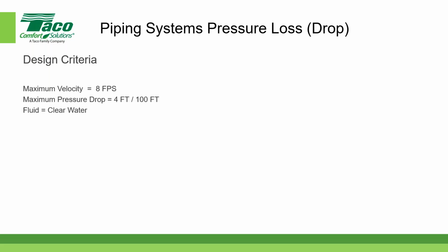And the other thing is that today's calculations will be based on clear water. Clear water is really a definition by the Hydraulic Institute that we use here at TACO. Hey, Rich, and basically, it just means that water has a specific gravity of 1.0, and nothing's added to the water. There's no glycol. It's just basic water. It's not considered potable water, but it's clear water.